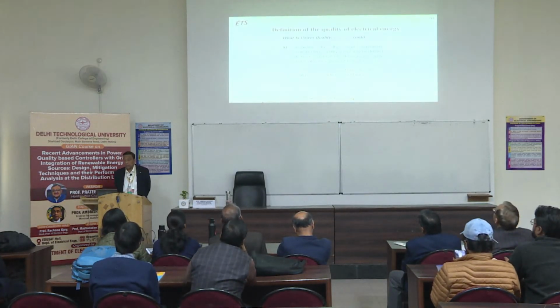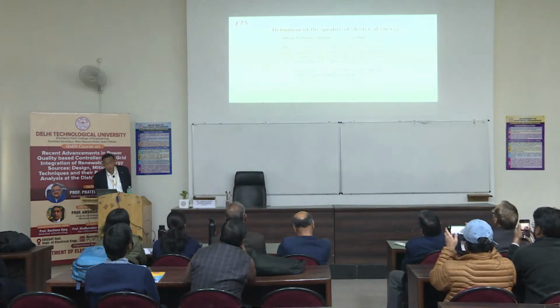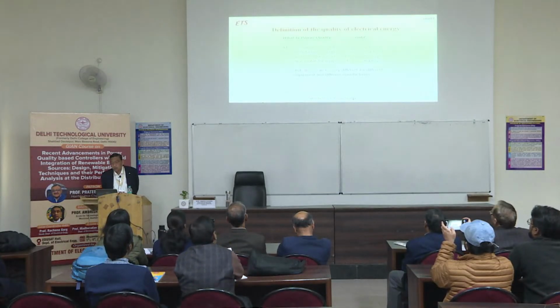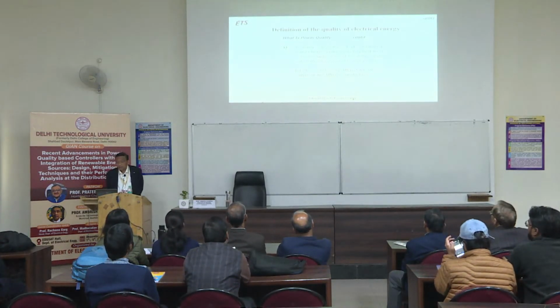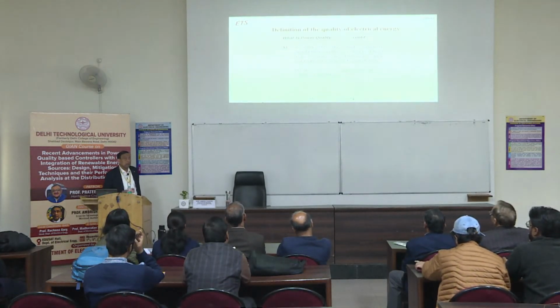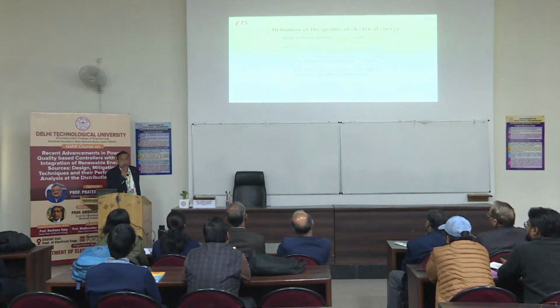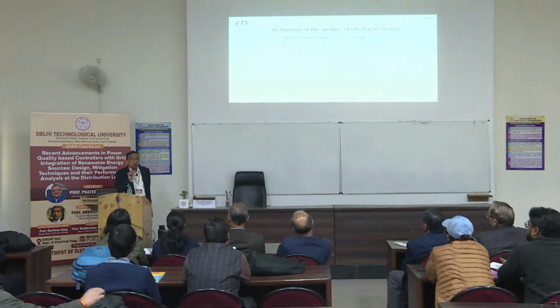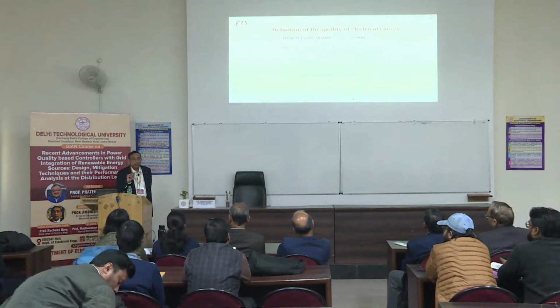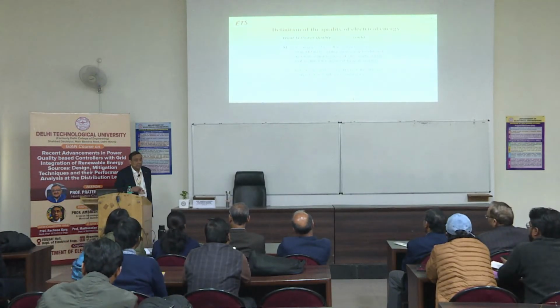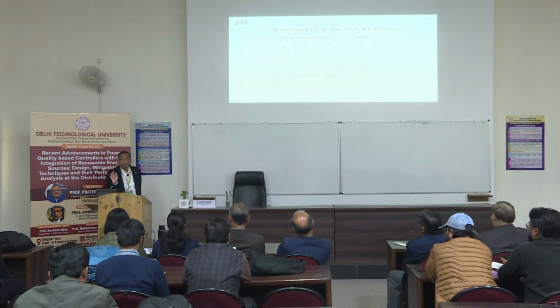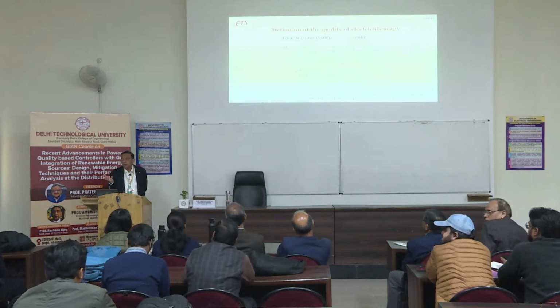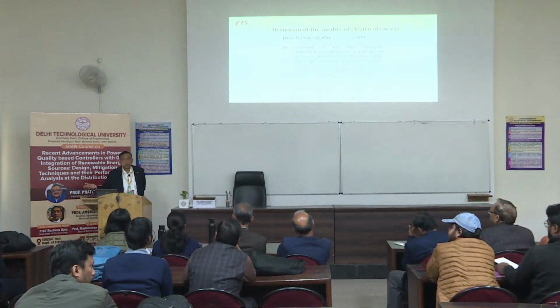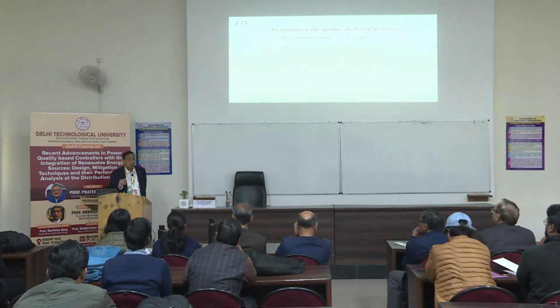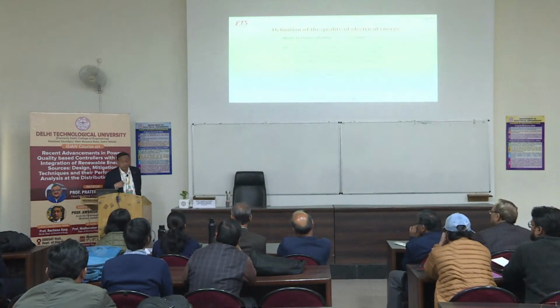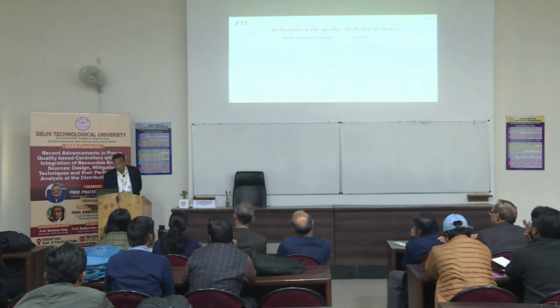According to the load equipment manufacturers, quality power may be defined as those characteristics of the power supply that enable the equipment to work properly. But these can be very different for different equipment and different manufacturers. For example, here you have 220 volts. I remember when I was a kid, sometimes the voltage was 180 or 190 volts. For the TV we used to have a knob to adjust the voltage. For some applications like radiators to heat the room, the voltage may vary, 190 volts or 230 volts, and it is fine, they will still work properly. But some equipment may fail or malfunction if there is a variation of voltage. So it depends on the equipment and the manufacturer, what their standard is.